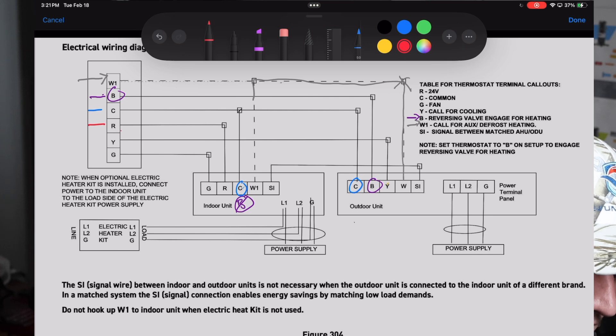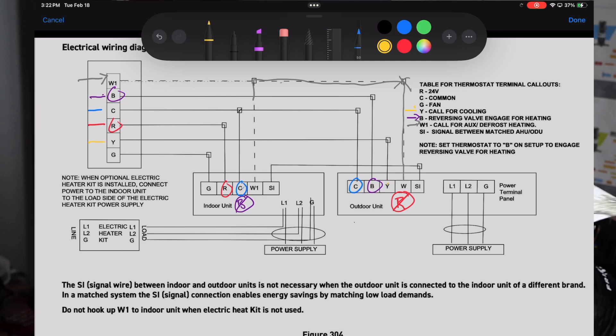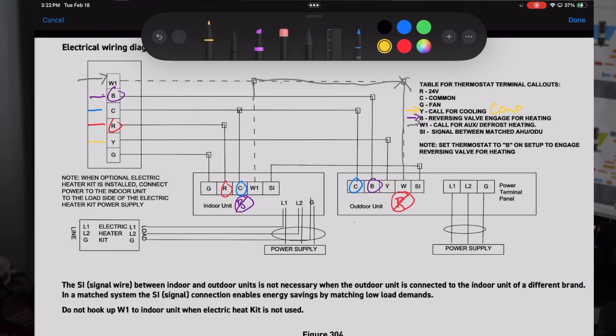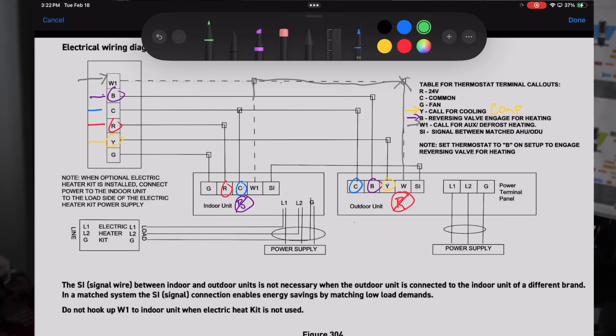Running down the line, your very next terminal is R. Now on a traditional heat pump you're going to have an R terminal at your outdoor unit, but you notice here that you do not. You only have your R terminal at your indoor unit and at your thermostat. The very next terminal you have is Y. Y has not changed at all. Here it shows it as a call for cooling. I think a better way to put that would be call for compressor, because during heat pump heating you're running your compressor. You'll have 24 volts on your Y terminal but you'll also have 24 volts on your B because we energize in heating. So Y is your call for compressor. You are going to have that Y at your thermostat and at your outdoor unit. You may or may not have a Y terminal on your air handler. If you have the matching breeze air handler, you're not going to have a Y terminal. If you have a different air handler and you have a Y terminal, go ahead and hook that up there.